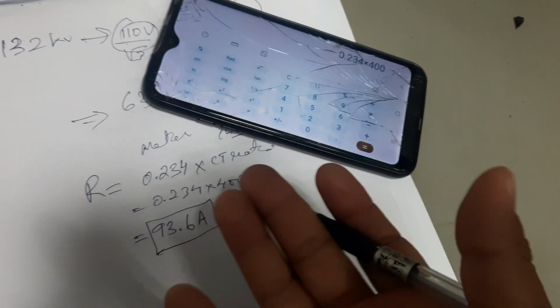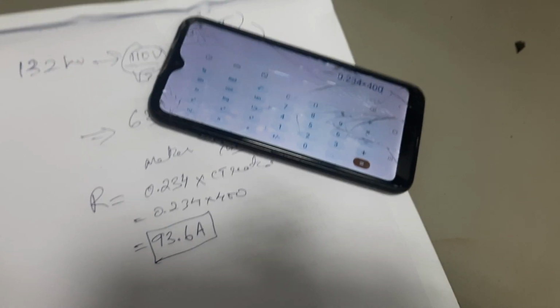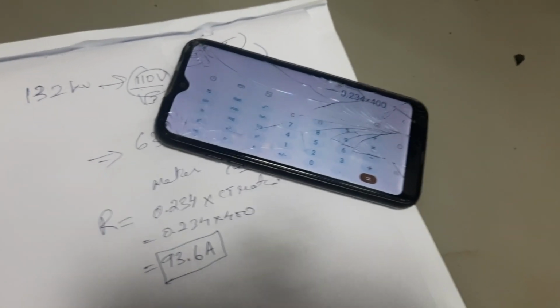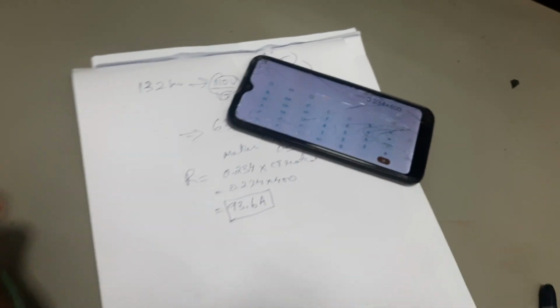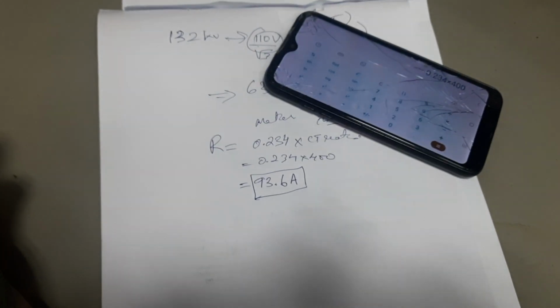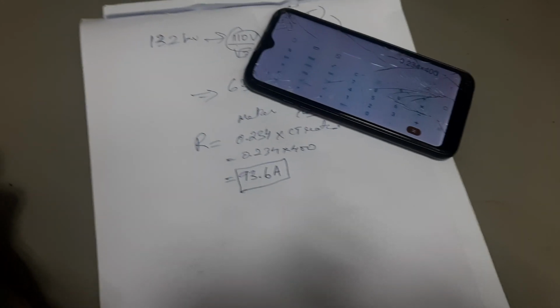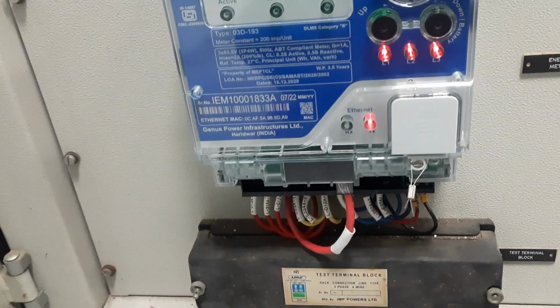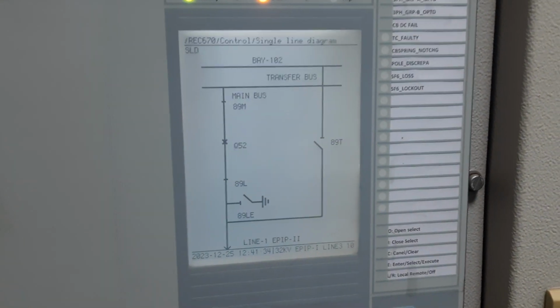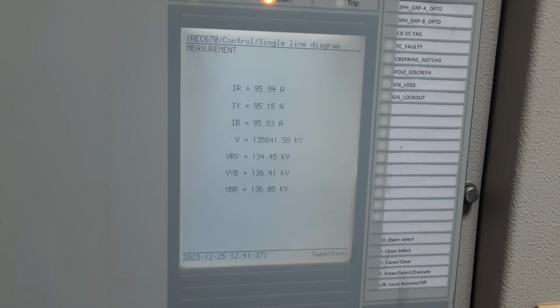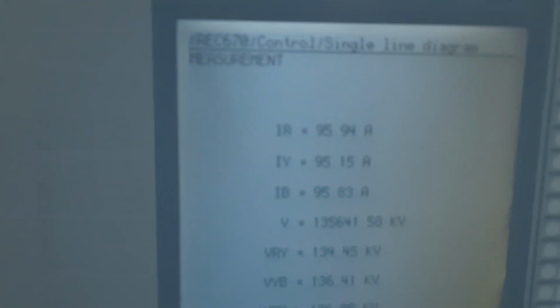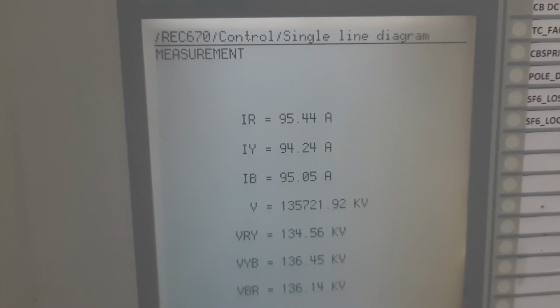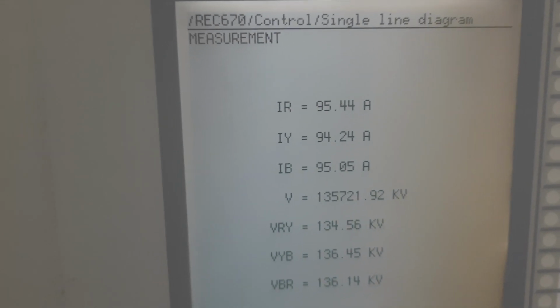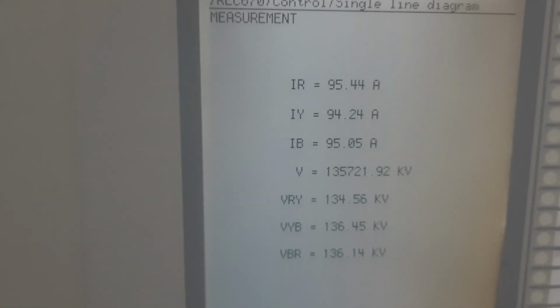I should be getting more or less, I mean it may change but not much, around 93, 94, in our phase current. Let us verify that from our BCU. See from the BCU what is the current. If I get this much, it's verified, there is no tampering of the meter. Okay, we are in BCU now, so let us just go forward. So this is our current, IR. My calculated value comes around 93 and this is 95, more or less, because it keeps changing also. So it's correct, that means I'm getting the right values. So the meter connection is correct. Okay, this is how you verify the meter.